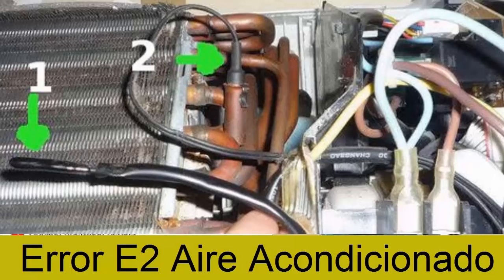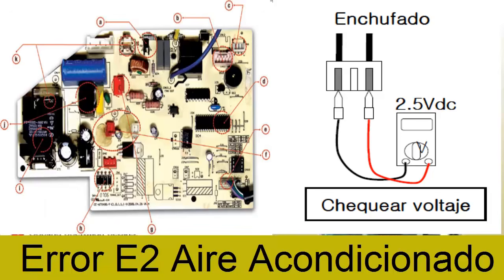4. Check for a damaged electronic board. In very rare cases, the E2 error can be caused by a damaged electronic board. The electronic board controls the operation of the air conditioner. If the board is damaged, it can cause problems with the indoor ambient temperature sensor. To solve this problem, you will need to replace the electronic board.